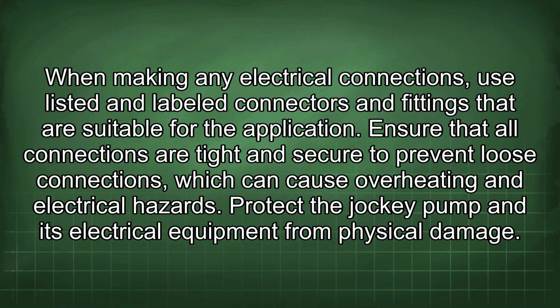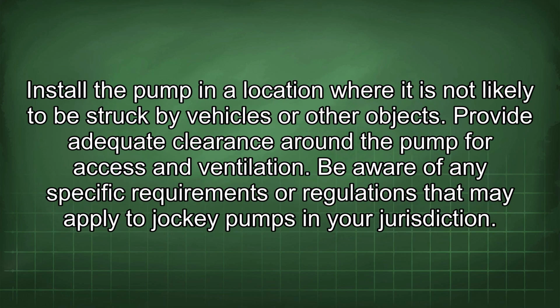Ensure that all connections are tight and secure to prevent loose connections, which can cause overheating and electrical hazards. Protect the jockey pump and its electrical equipment from physical damage. Install the pump in a location where it is not likely to be struck by vehicles or other objects. Provide adequate clearance around the pump for access and ventilation.